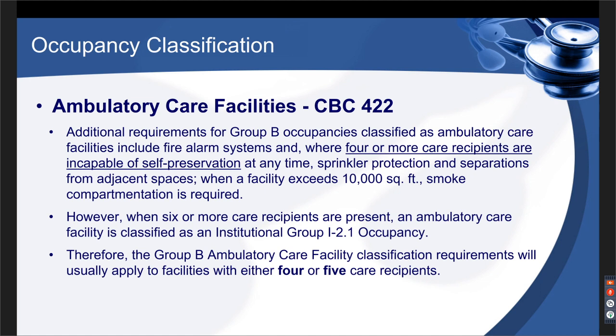There are sprinkler separation requirements, fire alarm requirements, and something that stands out with this one is where 4 or more care recipients are incapable of self-preservation at any time, then sprinkler protection is required, and we'll get into that in a little bit more detail in a minute. And then separations from adjacent spaces. The separations are also required in a fire partition. Separation is required from other tenant spaces and other public use spaces. We'll get into that a little bit more later as well.